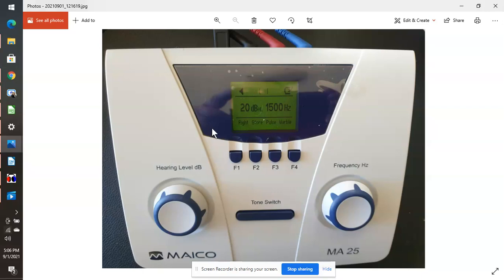In fact, once you're in, if you press F1 and F4 together, all you've got to do is press the down button 9 times until the word frequencies is highlighted, and then press F1, which is the change button, highlight 125 hertz, and then press F1, the change button, and it will change from on to off, and then just repeat that for 250 and 750 hertz.